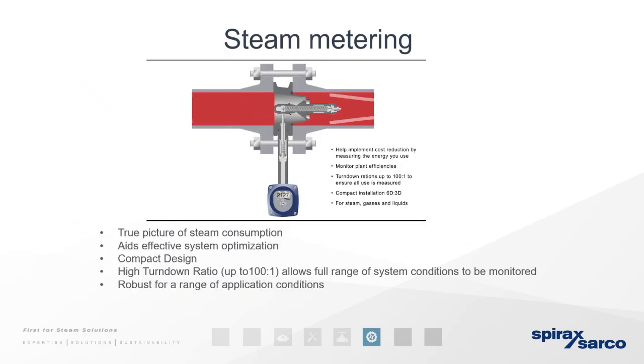So steam metering, as you can show here, gives you a true picture of your consumption. So it's always recommended that the mass of the steam leaving your boiler house is monitored. So you want to know how it helps you with the efficiency of your boiler. If your boiler is rated to produce a certain amount, but your meter is saying you're getting less, then that gives you an efficiency on the boiler. It shows that it's less efficient, for one. Again, I'm rattling through these.